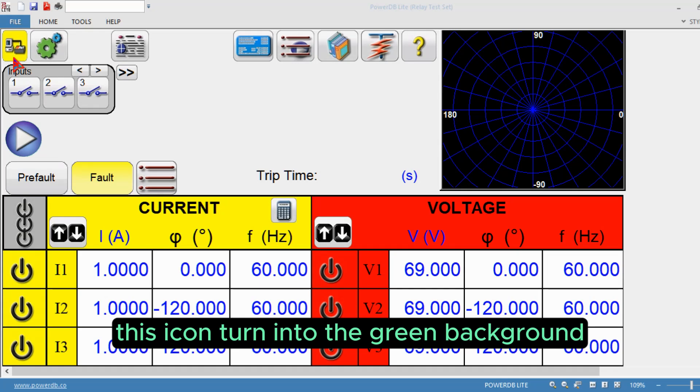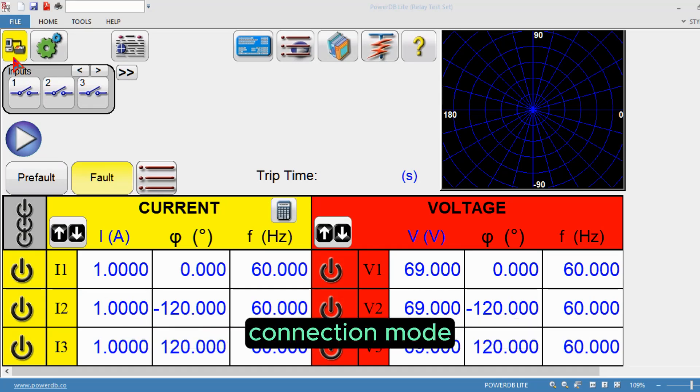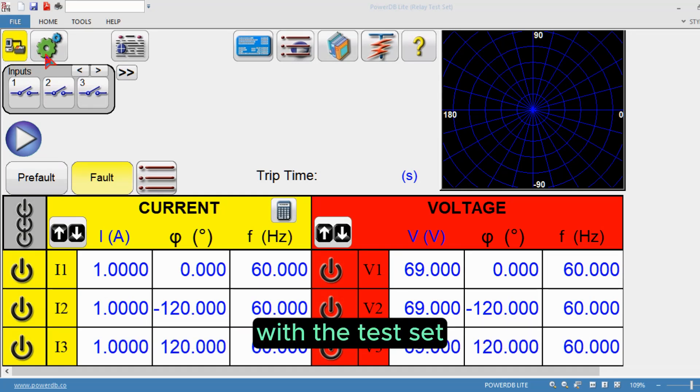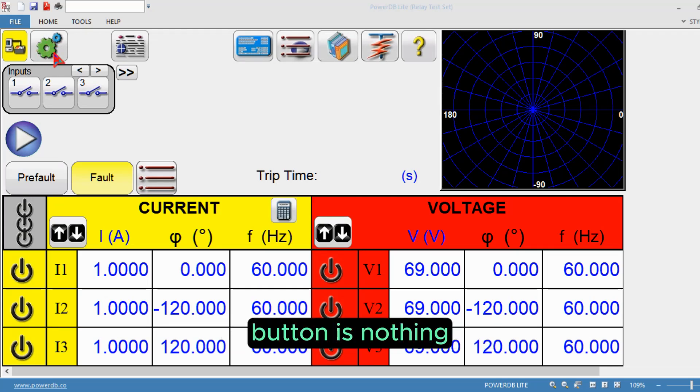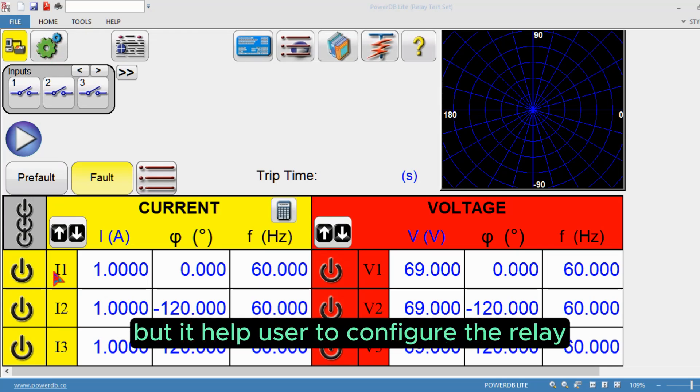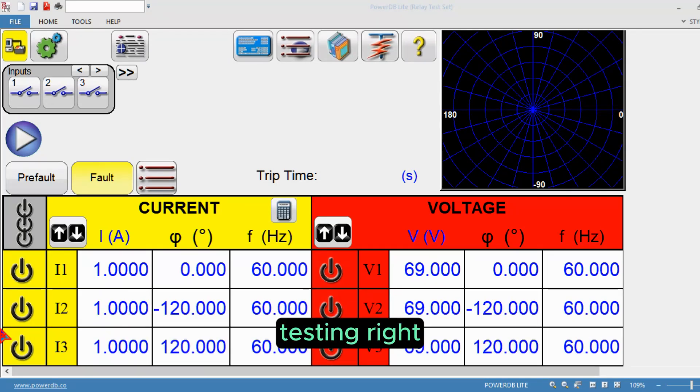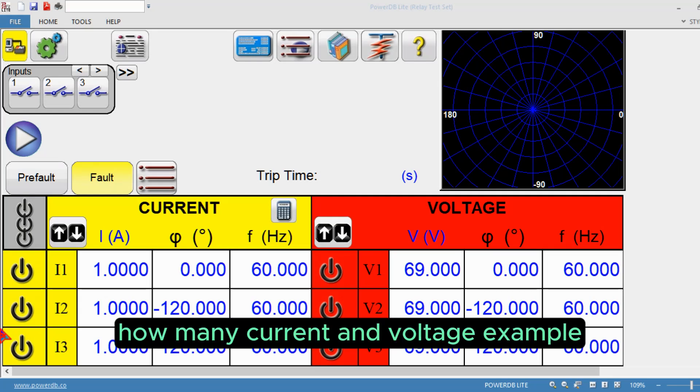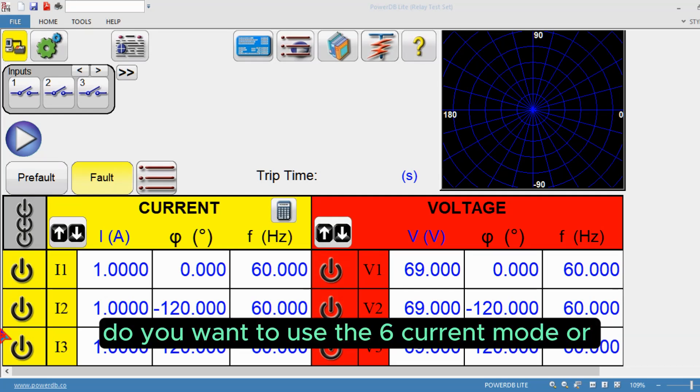The system configuration button helps users configure the relay test set and other functionalities to perform testing. For example, how many currents and voltages are required. Do you want to use six current mode or four voltage one current mode?